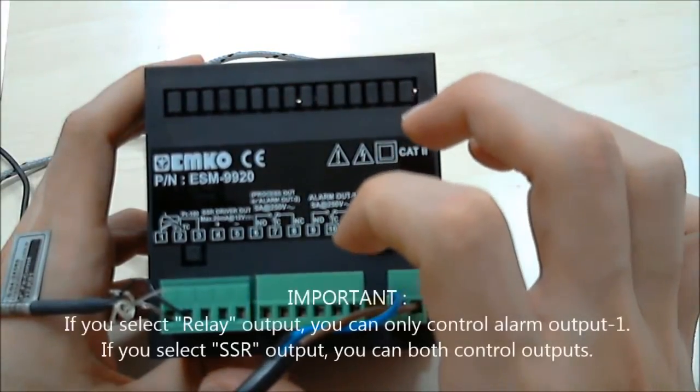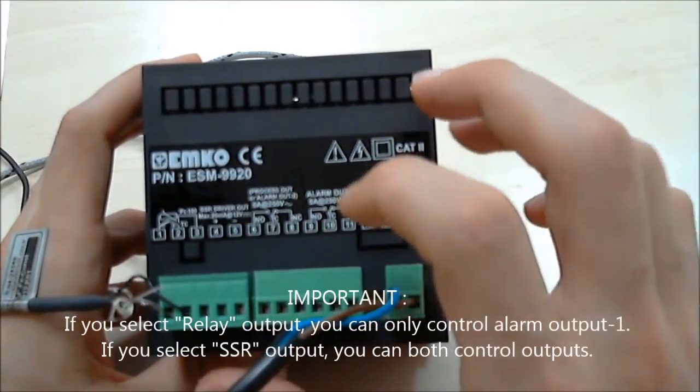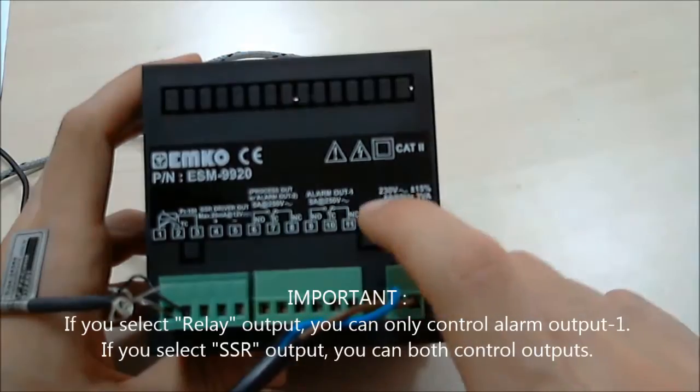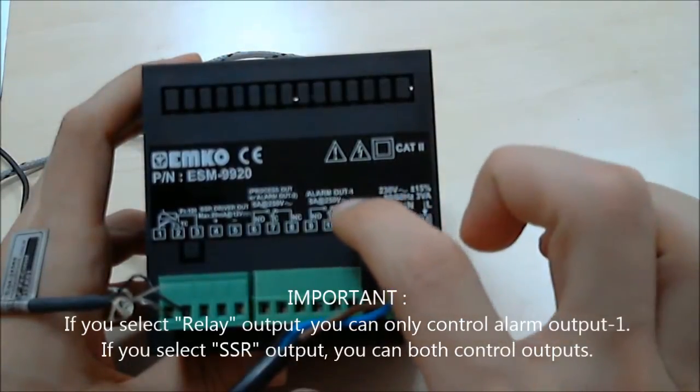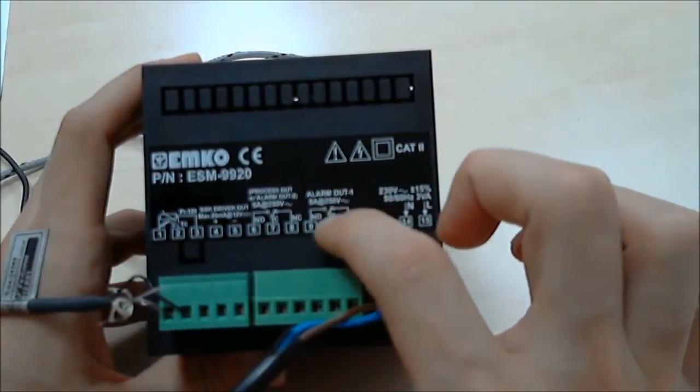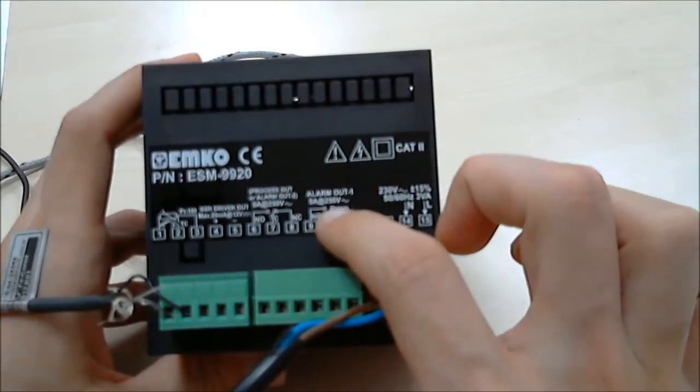But the important thing is here: if you select relay output control by parameters, only alarm output 1 will be active. So you can use this output for high alarm process.